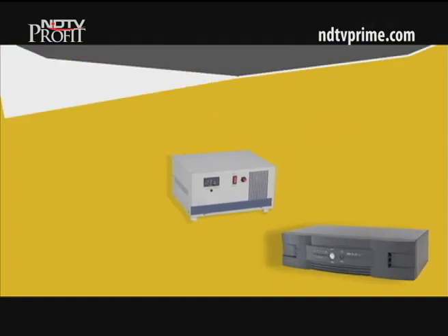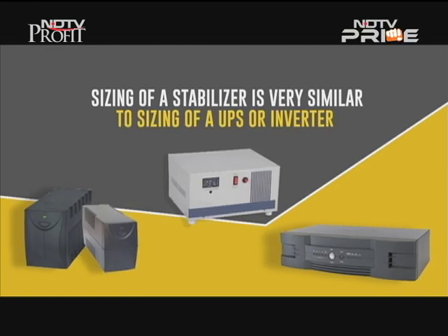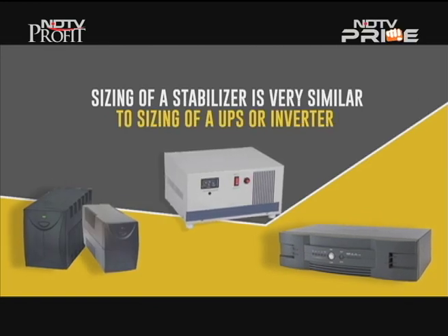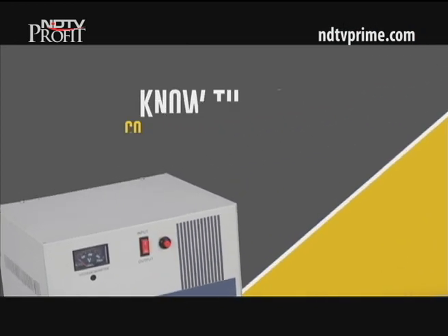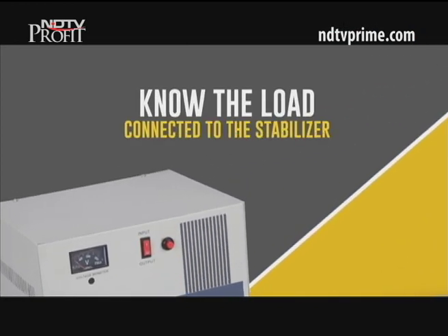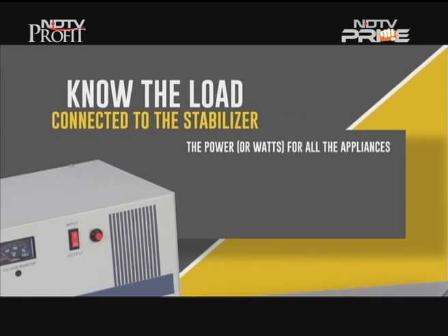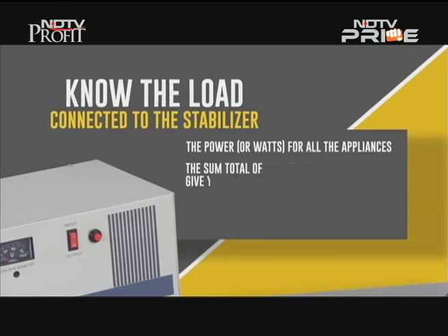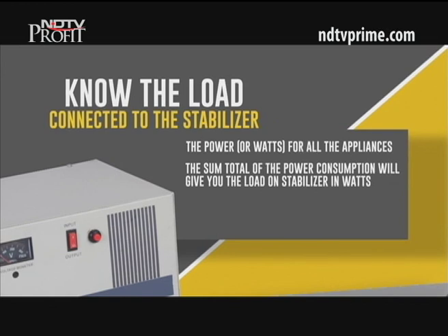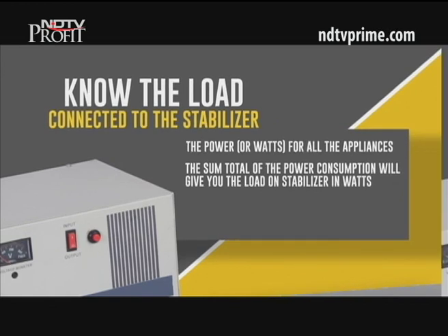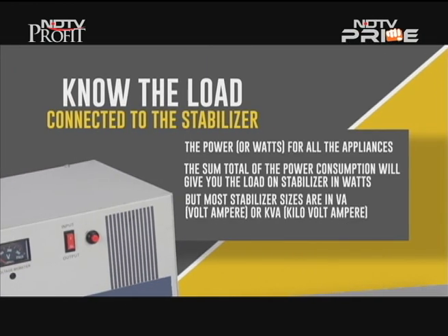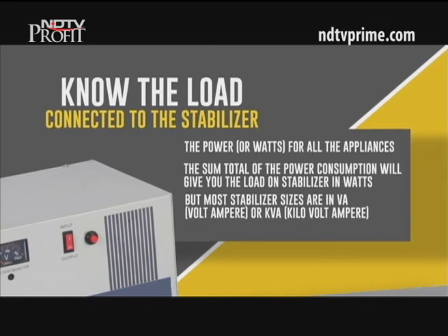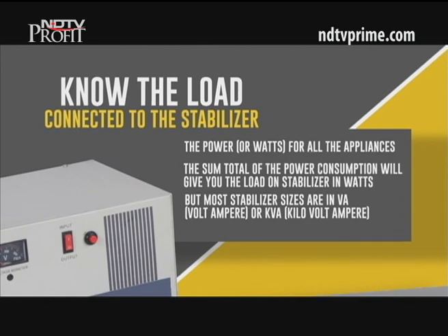Sizing a stabilizer is very similar to sizing a UPS or inverter. The most important thing is to know the load connected to the stabilizer. First, note down the power for all appliances that will be connected. The sum total of power consumption gives you the load in watts, but most stabilizer sizes are rated in VA, volt ampere, or kVA, kilovolt ampere, which equals 1000 volt ampere.